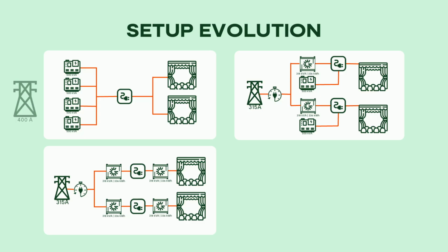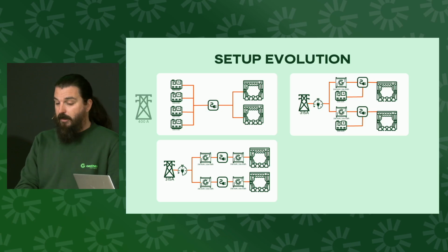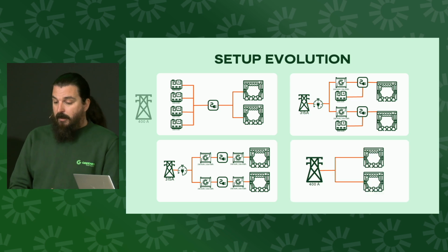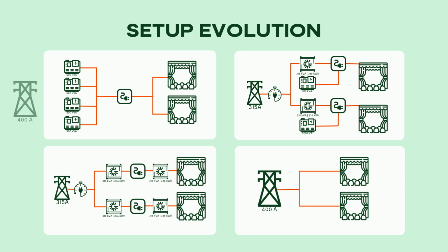So we doubled the capacity by putting a second serial battery in there. So now effectively for each leg you had 840 kilowatt hours of capacity available. And we completed the entire show there. And then the year after, they got a 400 amp grid in, and that was enough to run the entire show directly off grid with no extra equipment required. So, although it's a bit of a shame for Greener, it was a great result for the customer through the data gathered through our EMS, because it gave them the ability to push that grid connection from 315 up to the 400 they required to do the whole show. Yeah, exactly. And that's a really nice outcome for everybody.